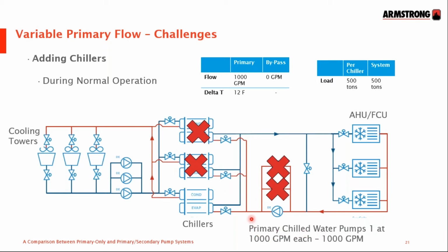So you'd think the first thing to do is to open the control valve of this chiller here. If we open the standard control valve, which opens and shuts in about 10 or 15 seconds, what's going to happen? Well, the chiller that is operating will see the flow rate through it dropping by half, because the other half will be going through this chiller, which is about to start up.